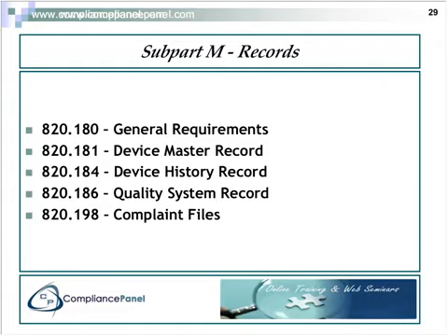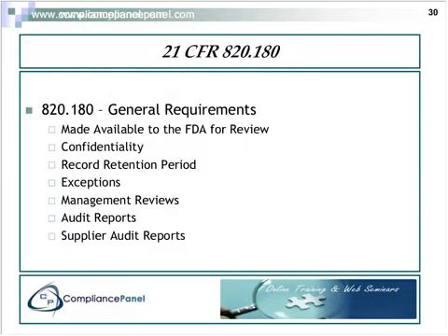The records defined here are not only for the benefit of showing a third party, but also for your own benefit, so that you have the capability of reviewing at a later date a historical record of the processes and their outputs. If there is an adverse event in the field, and you need to go back and ask how many of these devices did we build this way, what happened with this particular batch, or where did we use these components, you have all these records in place to answer those questions for yourself. So we're going to go through these individually so that we see a little more about how the records play a role here.